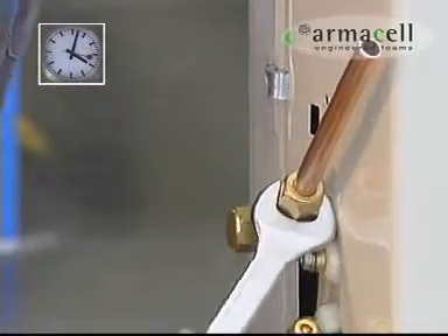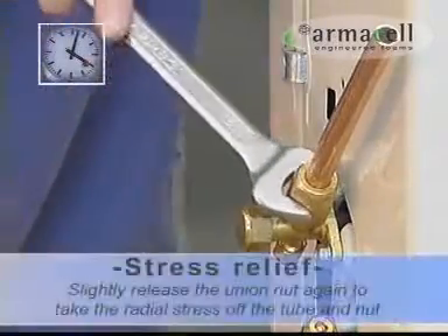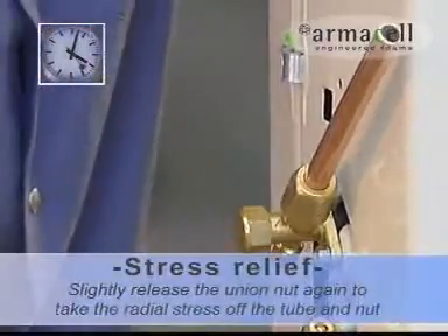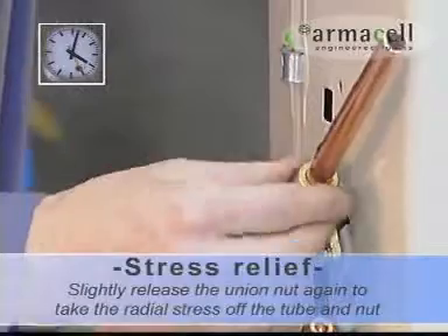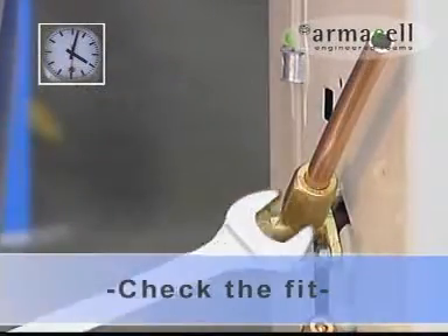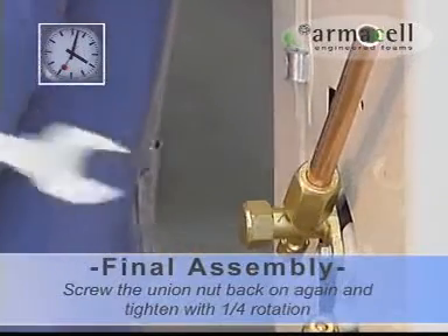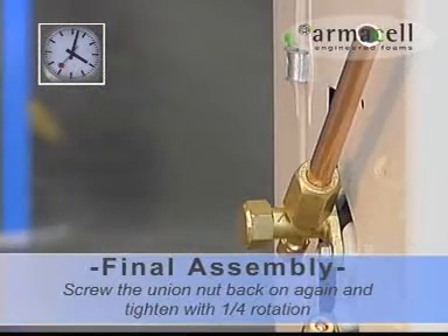Through the deformation, the compression ferrule is firmly mounted on the tube. Slightly release the union nut again to take the radial stress off the tube and nut. Screw the union nut back on again until finger tight, and tighten with one quarter rotation.